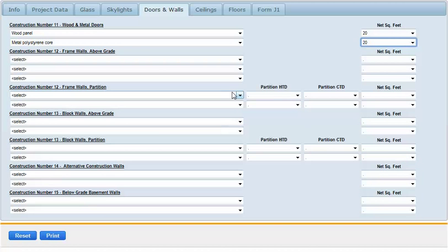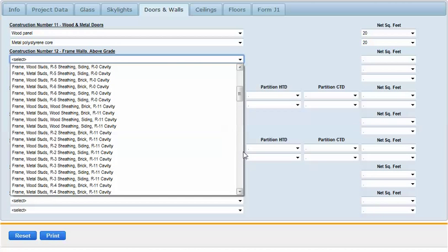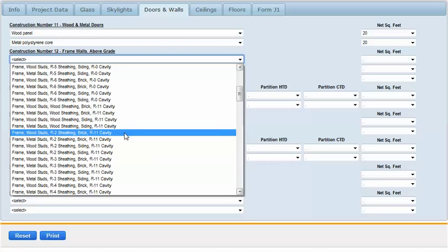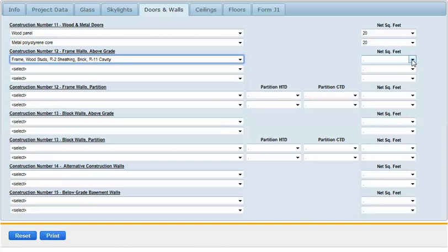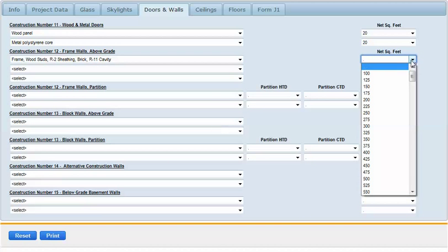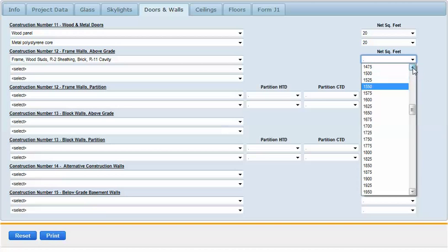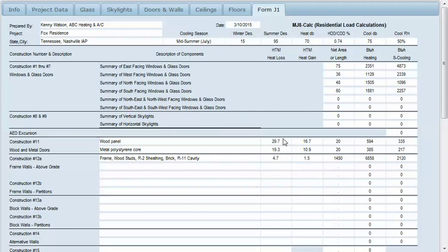Same thing with our walls. If there's any glass you deduct it out of the walls and put the net square feet. Here we're going to use R11 cavity with R2 sheathing and brick frame walls, wood studs. I actually have 1440 net square feet but the drop-down boxes are in increments of 25, so we'll use 1450. Looking at the J1 form you can see that our two doors and wall section have been transferred over.